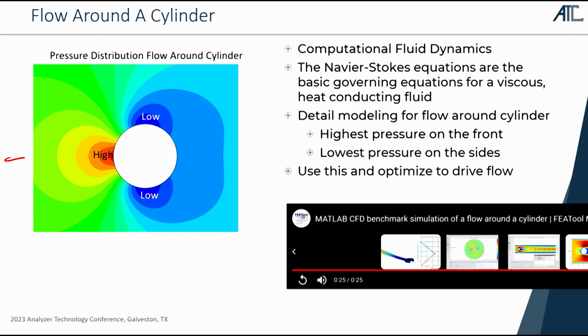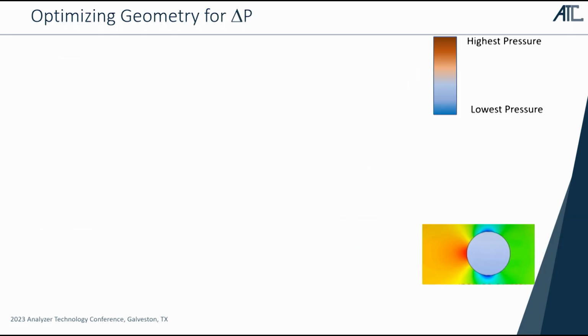The important thing to get from this is that if you solve the Navier-Stokes equation, if you do computational fluid dynamics, you find the high pressure region is out in front of the probe, and the lowest pressure regions are on either side of the probe, or that cylindrical object that's in the pipe. So how do we want to use that? Well, we know flow likes to go from high pressure zones to low pressure zones. So if we could find a way to create flow between the front of that pipe and the sides of that pipe, we could use it to drive flow through a loop. We'll talk a bit about how we do that. I'm going to be using reddish colors to indicate where the higher pressures are, and blue to indicate where the lower pressures are.